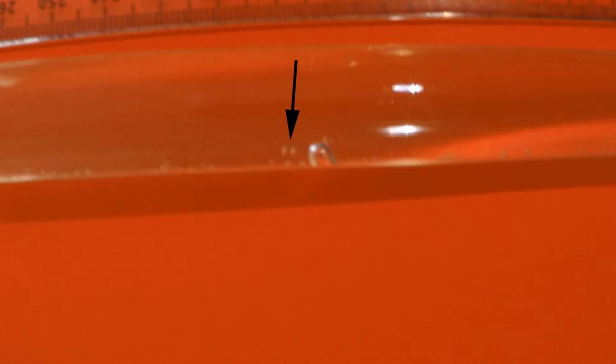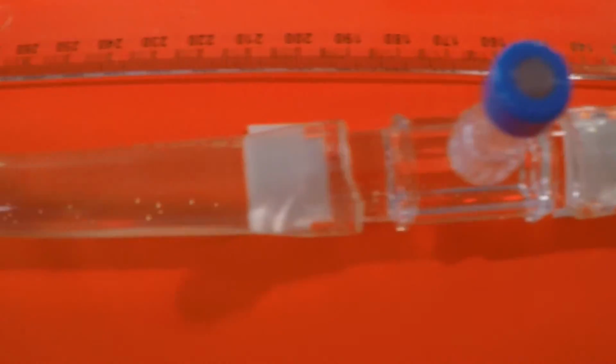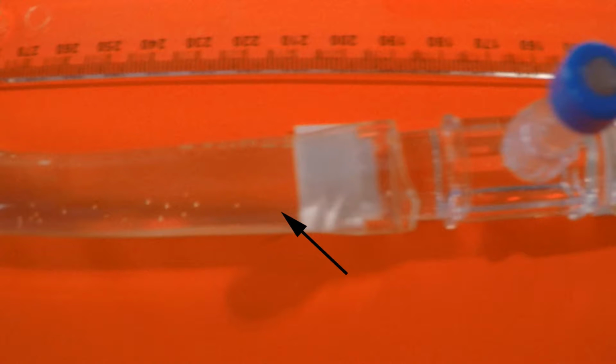In the next video clip, the tubing is again fully clamped and the camera is turned on its side as we watch buoyancy forces acting on various bubble sizes. A large bubble, approximately 2,500 microns, adheres to the side of the tubing as it ascends. Notice that the two smaller free-floating bubbles indicated by the arrow are traveling faster than the larger bubble attached to the tubing wall. Now observe the area indicated by a second arrow to see the buoyant forces of the larger bubble in action, as the bubble becomes detached from the wall when it contacts the tubing connector.